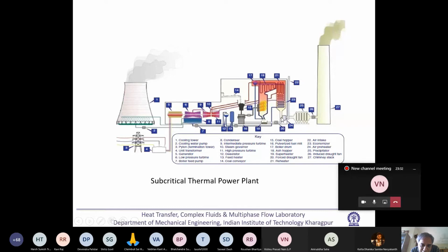What is the outgoing hot air? White line is the outgoing hot air. And this is a heat exchanger where these two airs come in, not direct contact, but come in contact, so that heat exchange becomes possible. So here there is a fan for the incoming air. Here there is a fan for the outgoing air, and in between we are having the air preheater.